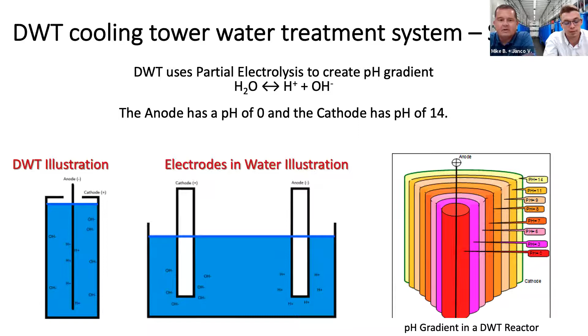Again, like I mentioned, we're using partial electrolysis, and this allows us to use low voltage DC current on the anode itself, putting a pH gradient into the cathodic surface, the cathode reactor. This environment allows two things to happen: one, the generation of chlorine and hypochlorous acid allows us to actively sanitize the water, and then the high pH on the wall of the cathode allows us to pull unstable calcium, magnesium, and scale-forming mineralization. It allows for a much more cohesive and complete treatment of the process water.